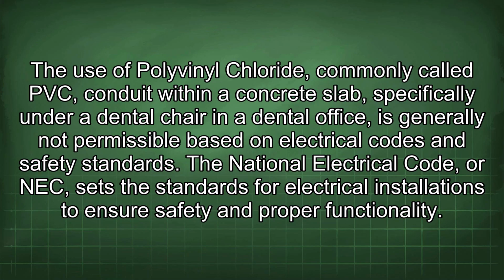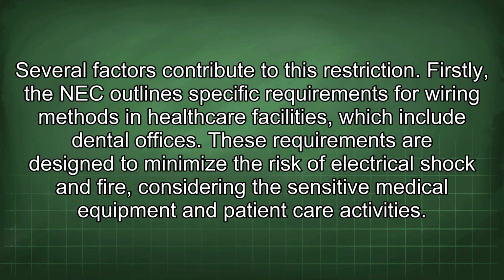The use of polyvinyl chloride, commonly called PVC conduit, within a concrete slab, specifically under a dental chair in a dental office, is generally not permissible based on electrical codes and safety standards. The National Electrical Code, or NEC, sets the standards for electrical installations to ensure safety and proper functionality. Several factors contribute to this restriction.